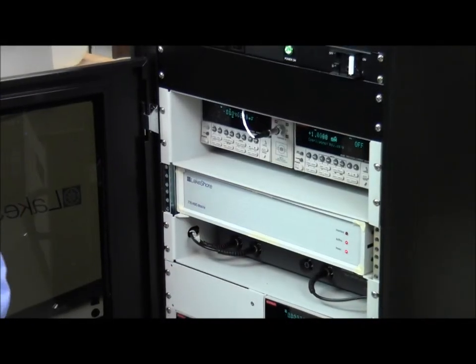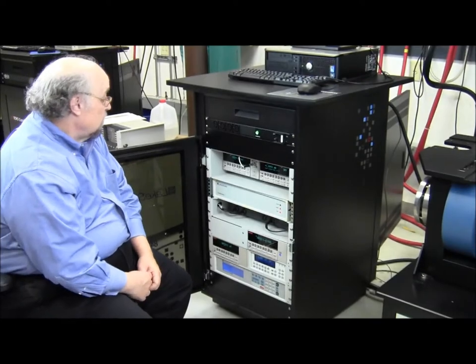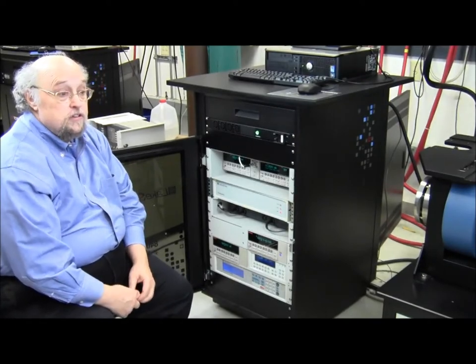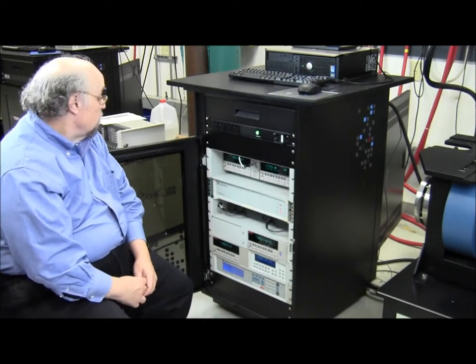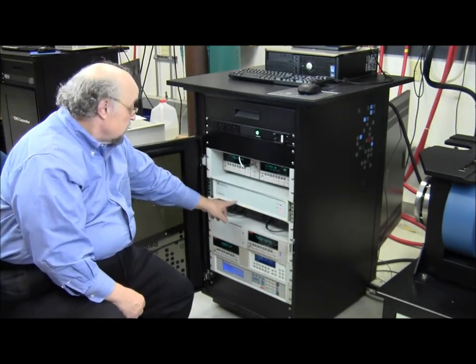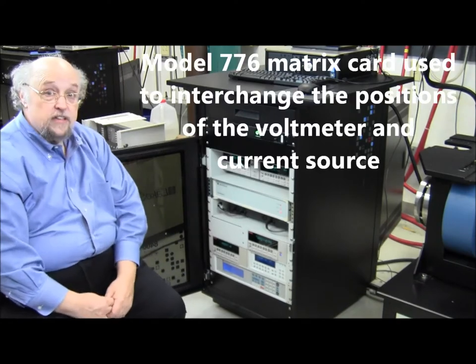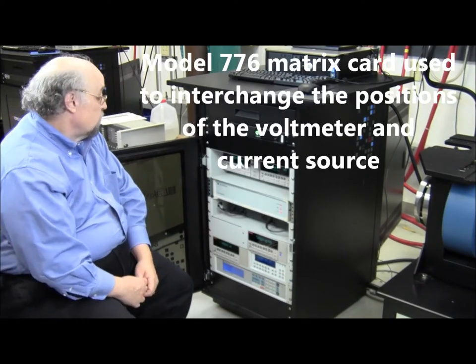To do a hall measurement you need to be able to interchange the positions of the voltmeter and current source to measure resistivity and hall voltages. So in order to do that you need a matrix card and that's what this box is. It's the Lakeshore Model 776 HMS Matrix Card.